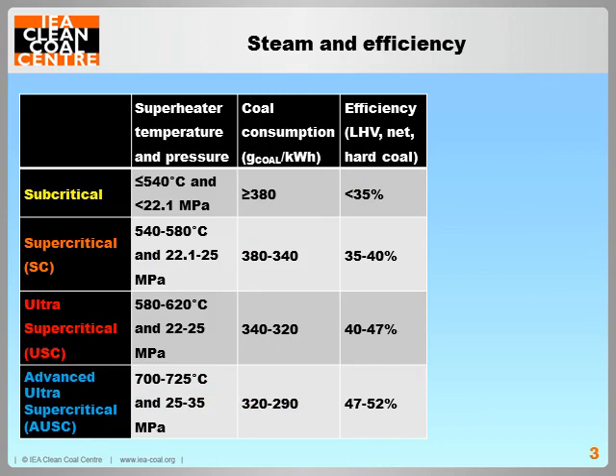Increasing the electrical efficiency of a pulverised coal-fired power plant guarantees lower coal consumption and lower emissions. One of the most effective ways to increase the efficiency is to increase the steam temperature in the steam cycle. The next target is advanced ultra-supercritical steam parameters reaching 700 degrees Celsius and 50% electrical efficiency.